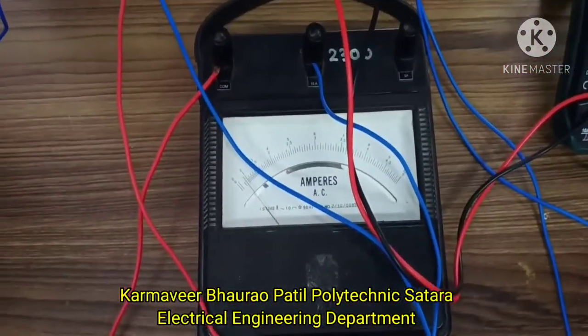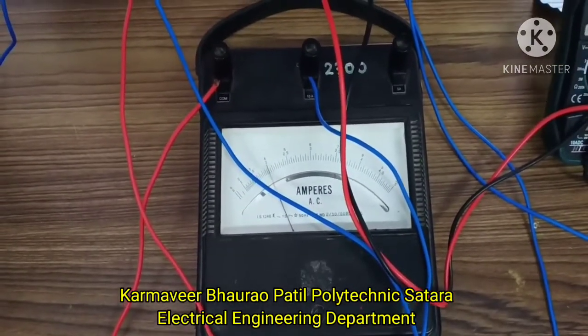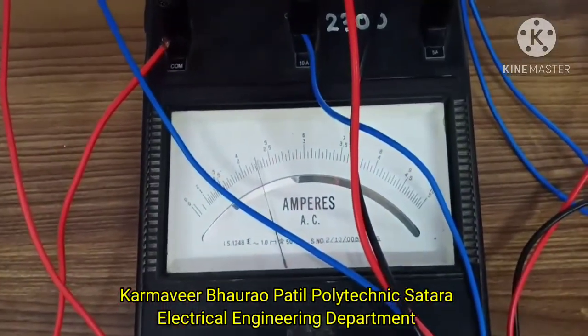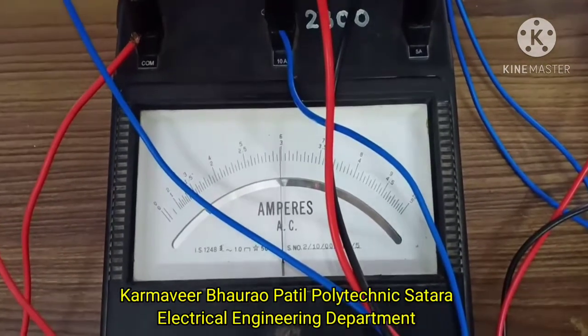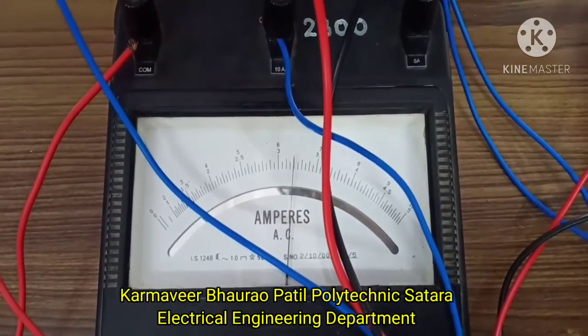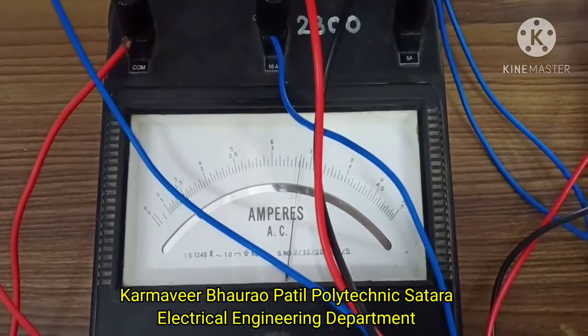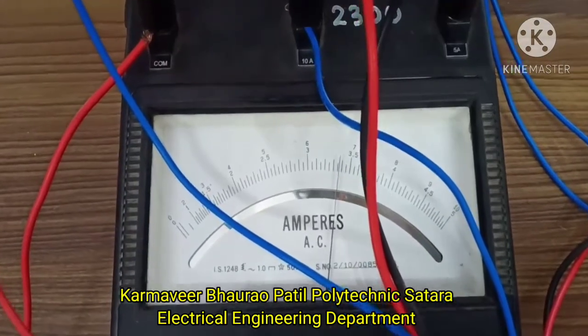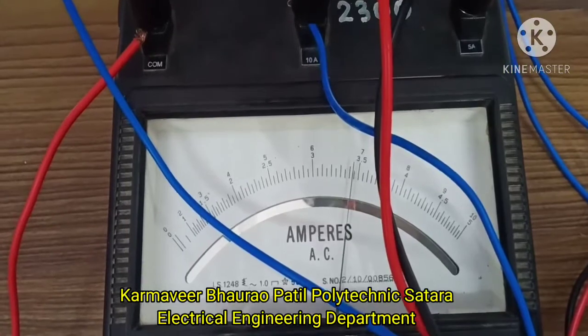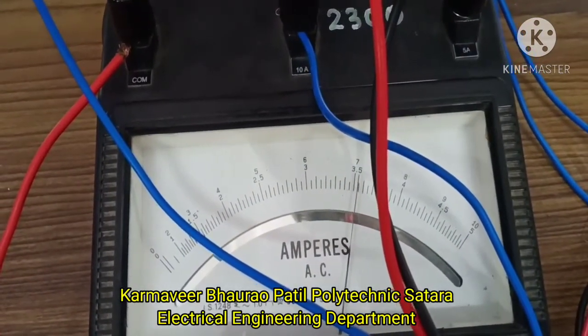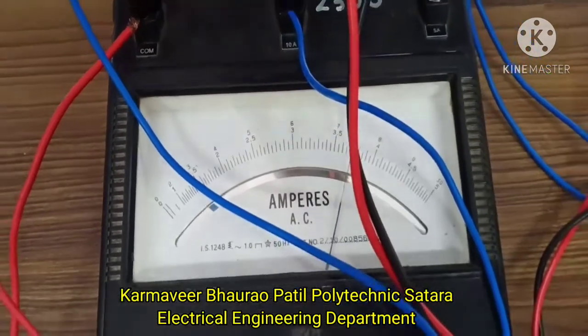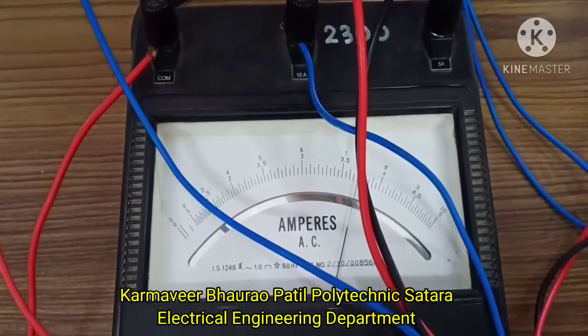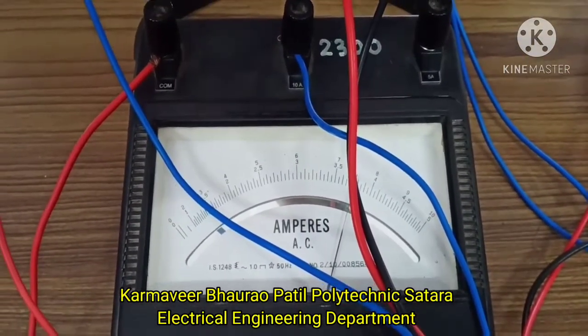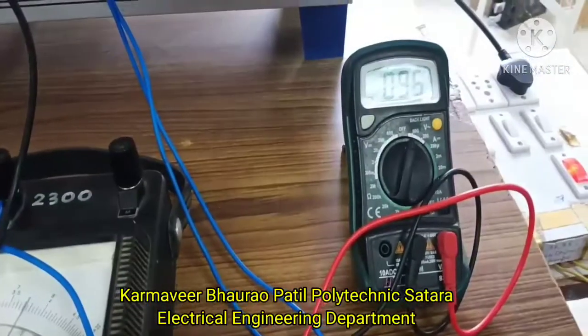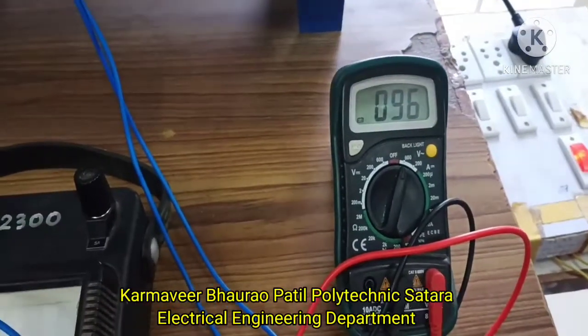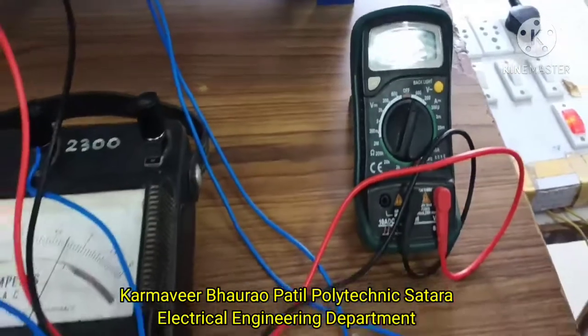So this motor has a rated current of 7.4. 7.4 is the rated current for this particular motor. Hence we will slightly increase the voltage, so that we get near 7 ampere current. We are getting 7.5 ampere rated current here. So we will note this down as ISC, that is the short circuit current when the rotor is blocked, and this voltage showing is the short circuit voltage when the rotor is blocked.